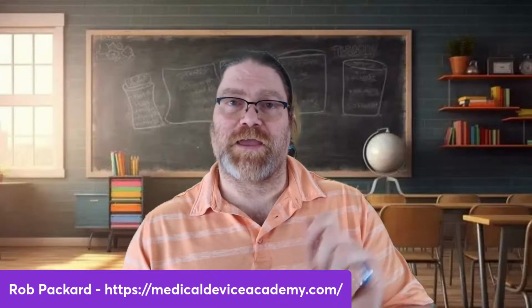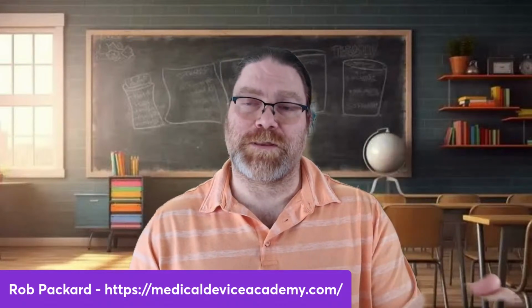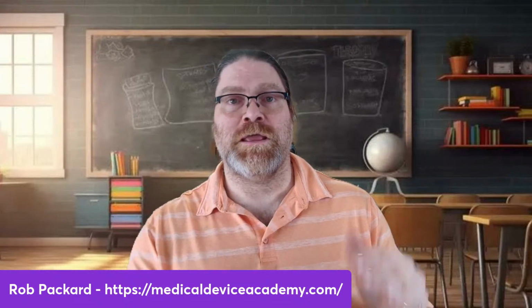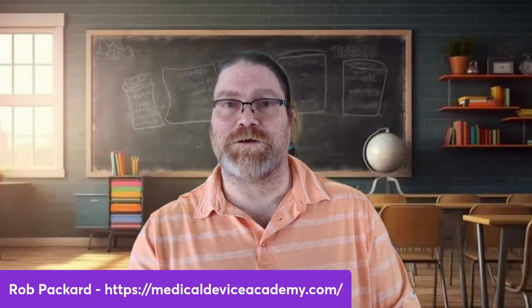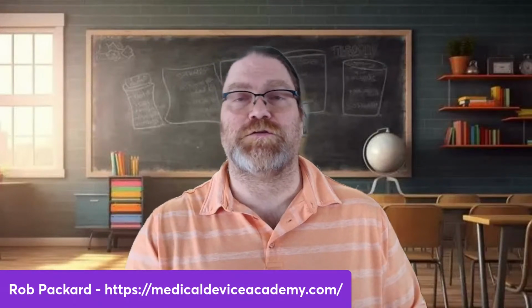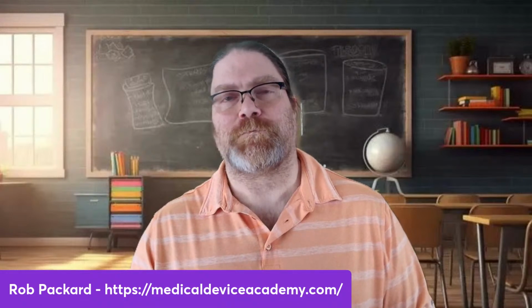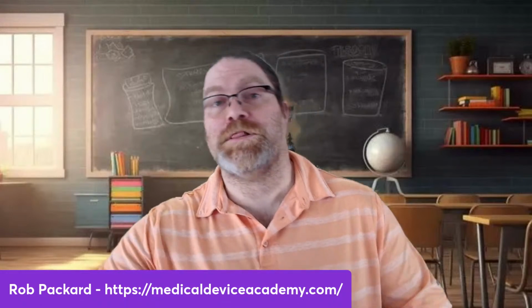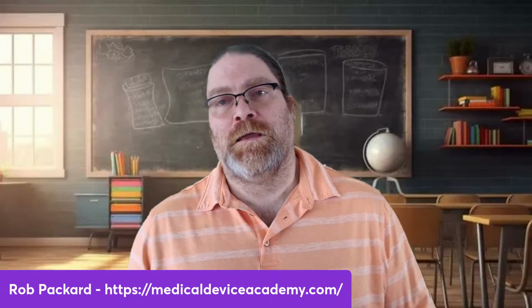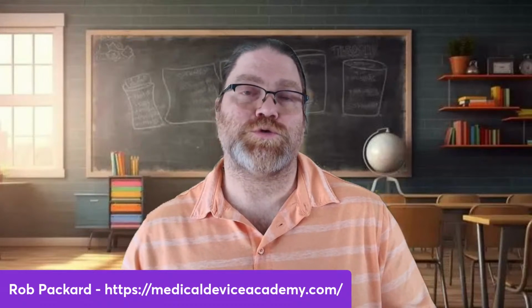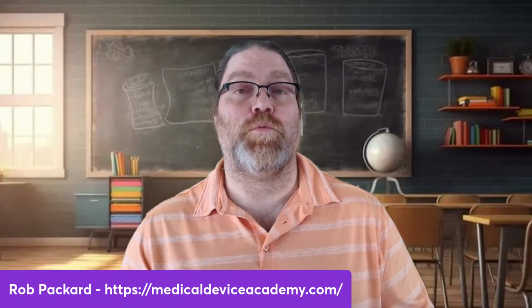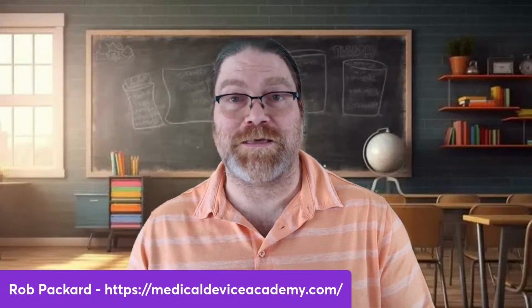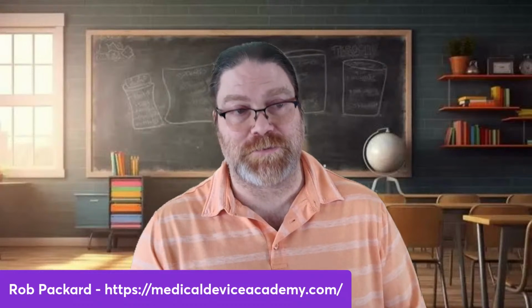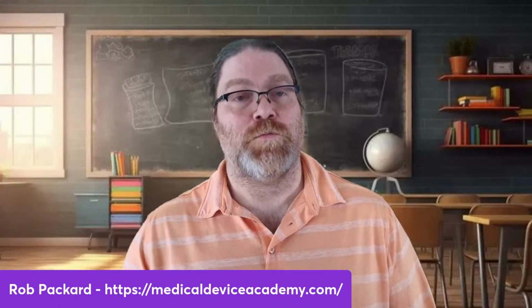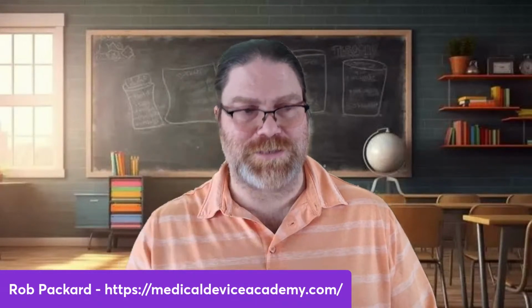So we say to the FDA, here's the version we used for the summative testing, here's the final version, and the changes are redlined here, and we made these changes in response to feedback in the testing. Now, if we had to completely overhaul it, then that would be a situation where we probably have to repeat the testing, but we wouldn't completely overhaul it unless you failed the test in the first place. So if you're passing it, we don't want to make big changes, just little itty bitty changes.